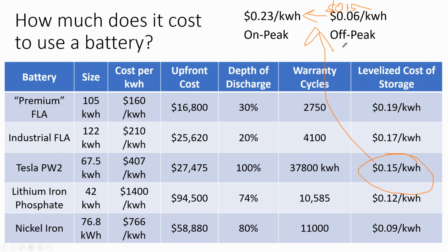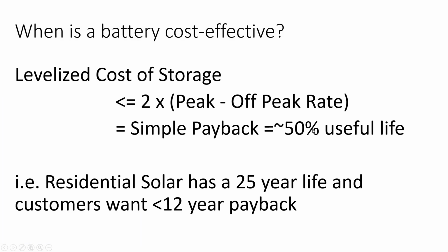You're almost just spinning your wheels by charging the battery off peak and then discharging it on peak. You're really not saving any money, you're just using your battery to try to recover the cost of your investment. But there's a limited warranty, or a limited life, on these batteries. And if you take the warranted performance of that Tesla Powerwall and divide it by its cost, you realize that in most cases you need a time-of-day differential that isn't 6 cents versus 23 cents, but more like a 30-cent differential for that day trading of electricity to make economic sense.